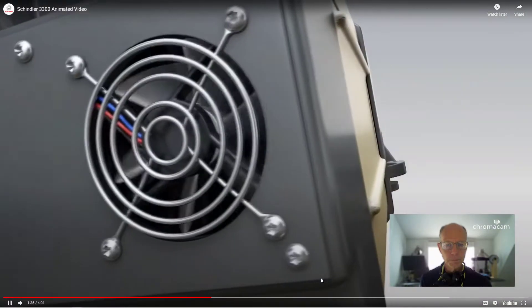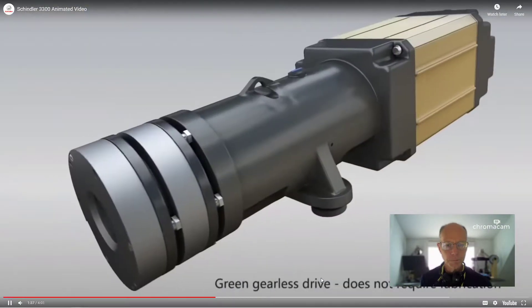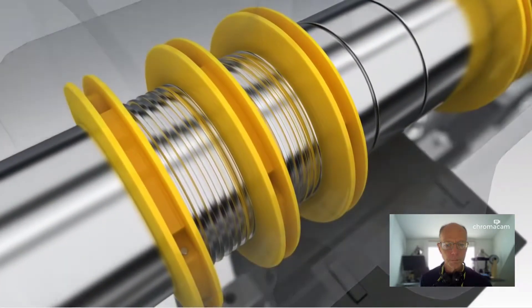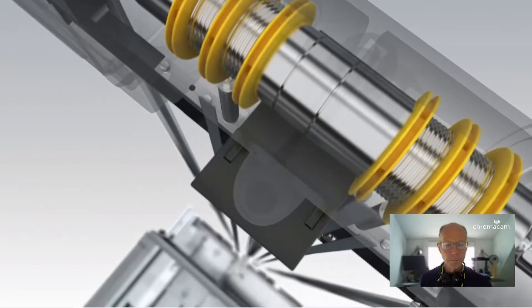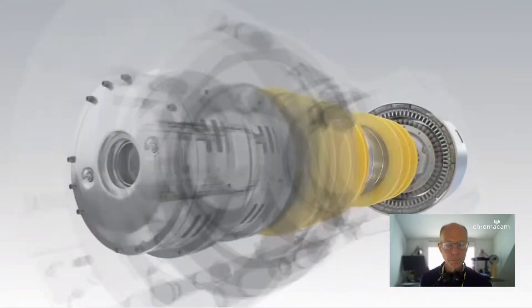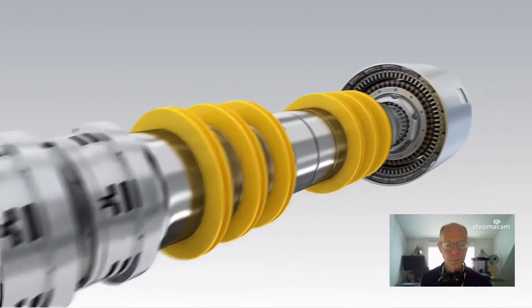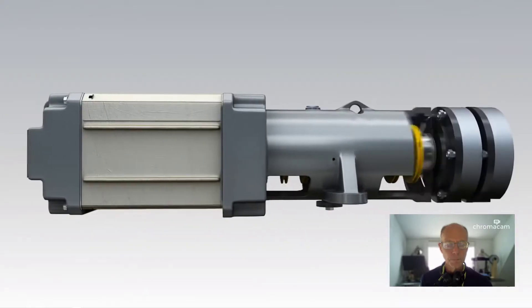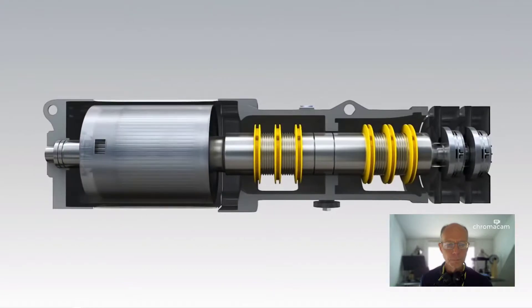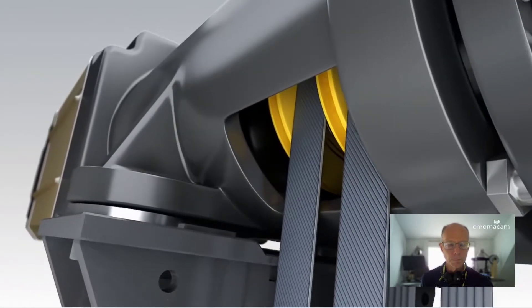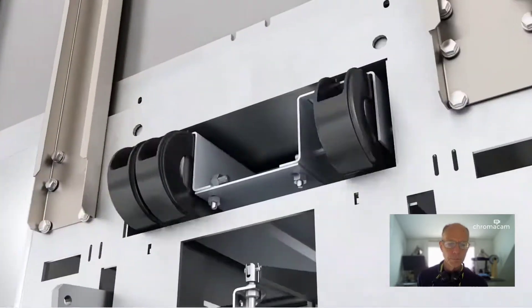These advantages enable Schindler to utilize a highly efficient small gearless traction machine with best-in-class motor efficiency and performance. The motor adopts an axial design that gives a high starting torque. With an integrated long-pass traction shaft, load is distributed over both ends, thus leading to secure and stable operation.